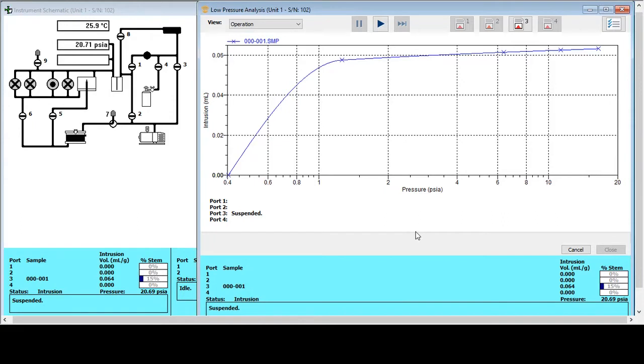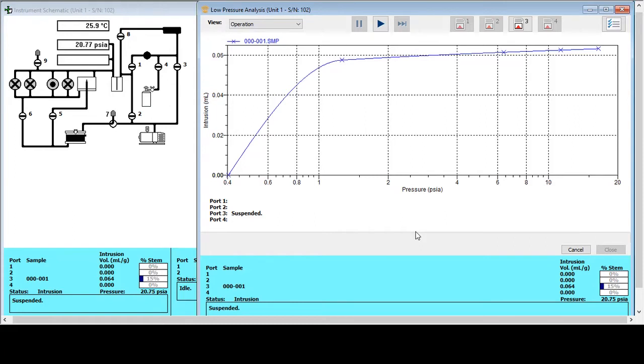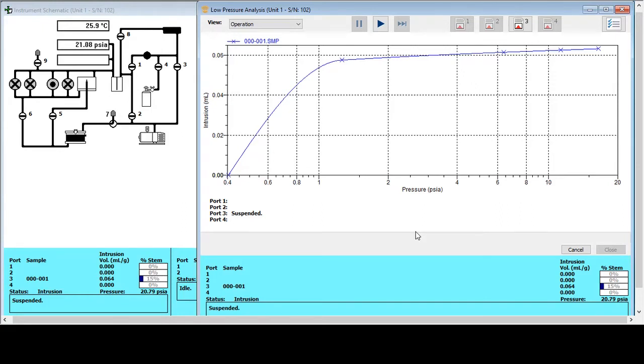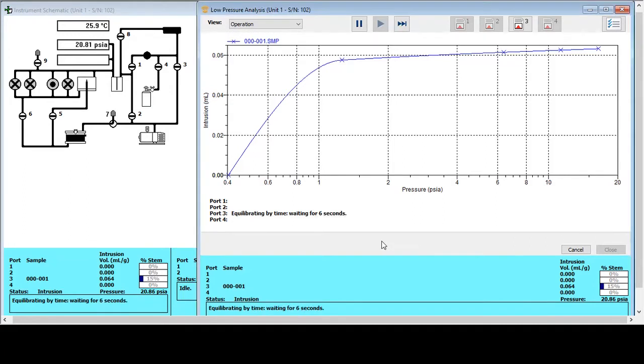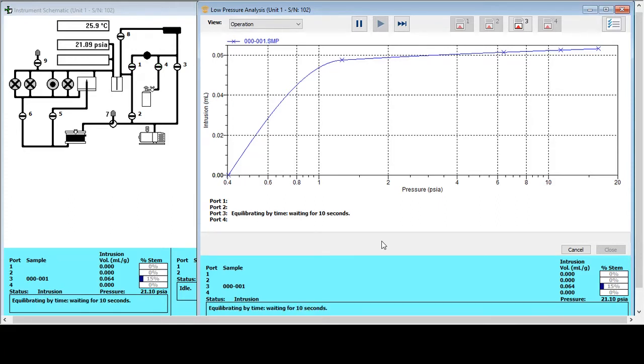So now the low pressure system has been fully evacuated and the penetrometer has been backfilled with mercury. That occurred at a pressure of 0.1 PSIA. So we're now back to measuring pressure in PSIA and that will continue all the way through the analysis now. We can now also work off of the right hand panel. And this shows the real time data collection. Now this was blank before because we hadn't actually reached the stage where mercury intrusion data was being accrued. But now we can see a plot of pressure on the x-axis by intrusion volume on the y-axis being generated. The y-axis at the moment is showing the absolute intrusion volume. By the time we finish the analysis and we generate our reports, that will be displayed as per unit mass of sample.